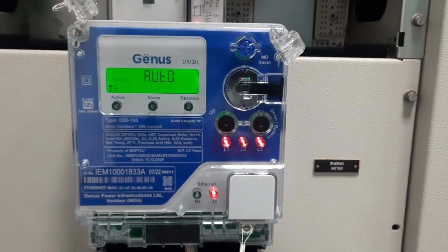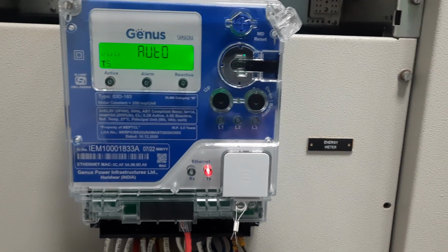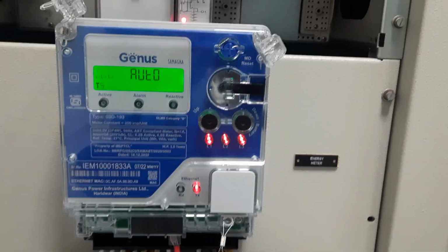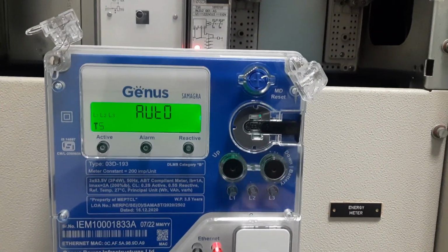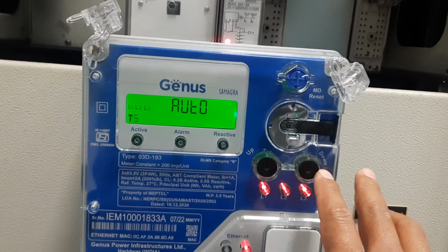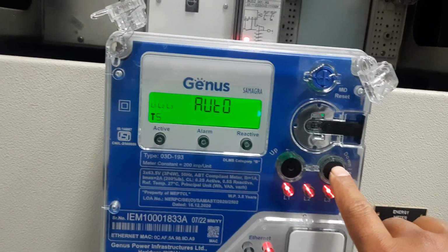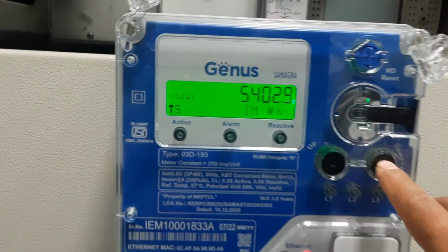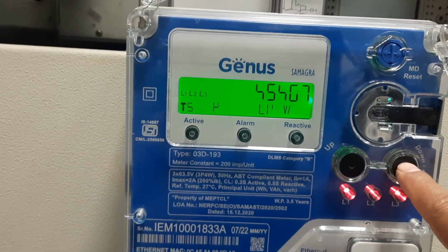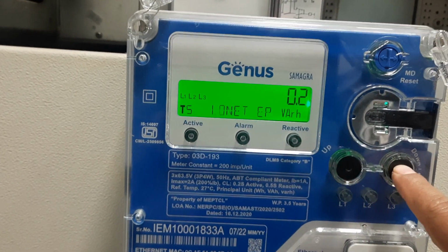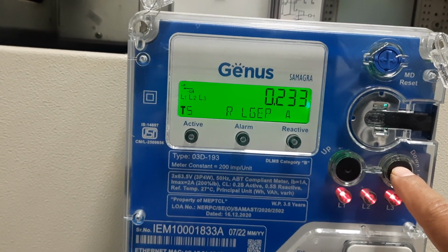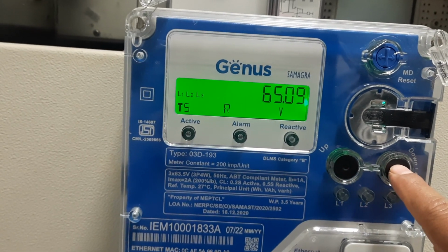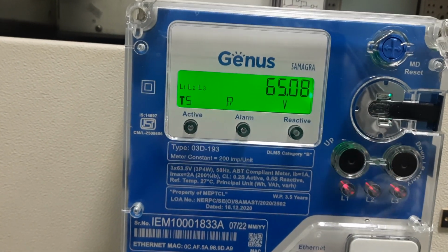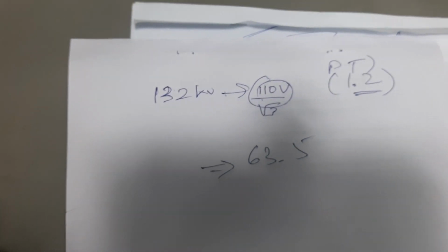I'll be checking whether the meter has been tampered with or not, because tampering is illegal as per the Indian Electricity Act 2003. See, the current indicators are all blinking, that means all of them are online. There is a current. Let us see the voltage. I have taken one phase, but for any phase it will be more or less the same. Our phase to earth voltage is 65, very close to our calculated value of 63. That means this is fine. Nothing is wrong with the meter, the connection is fine.